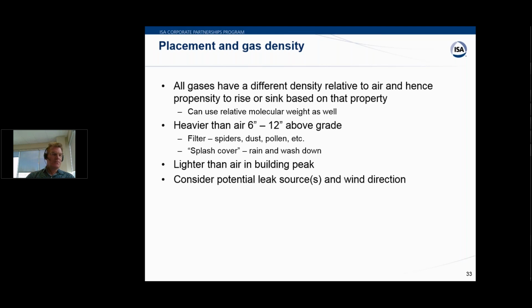And the other thing, of course, that's important, because these are point detectors, is having the detector in the right place. As we know, every gas has a different density relative to air, and air has a molecular weight of approximately 28. A lot of times you will get the specific gravity for a gas, SG. It's relative to air, which is 1. So obviously if your number is less than 1, then it will rise. If it's higher than 1, then it will sink.